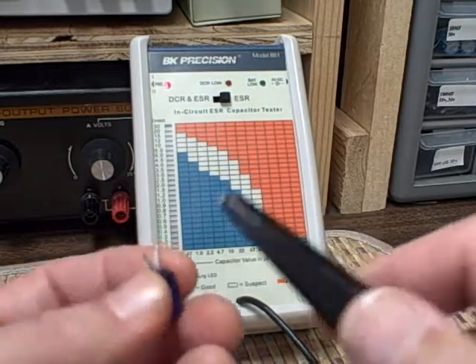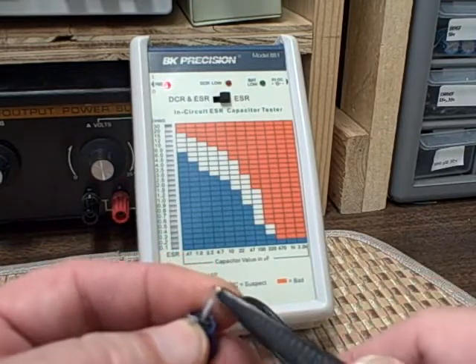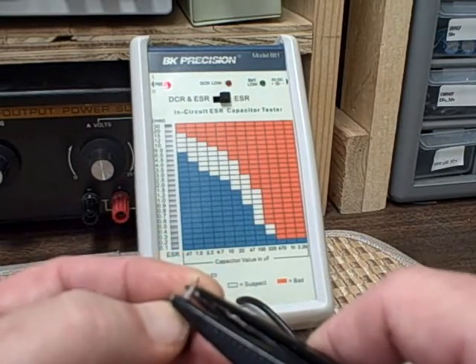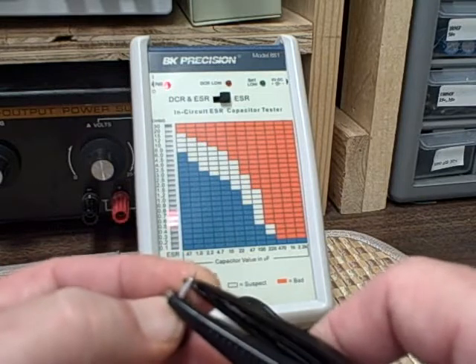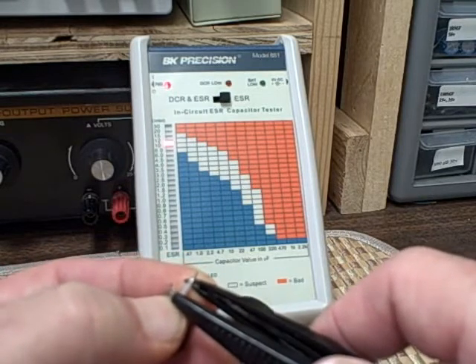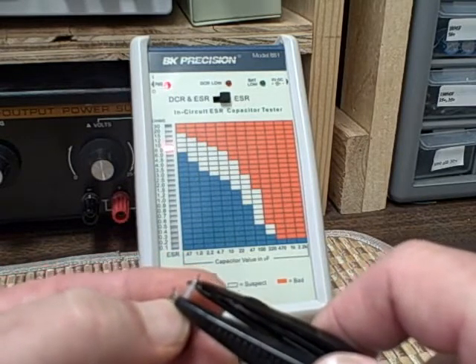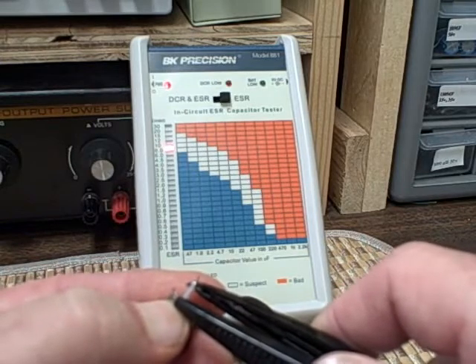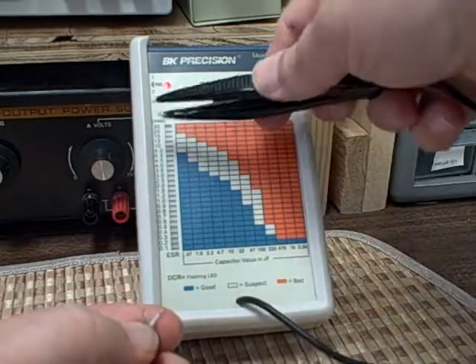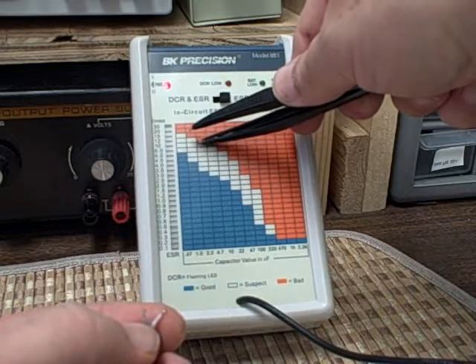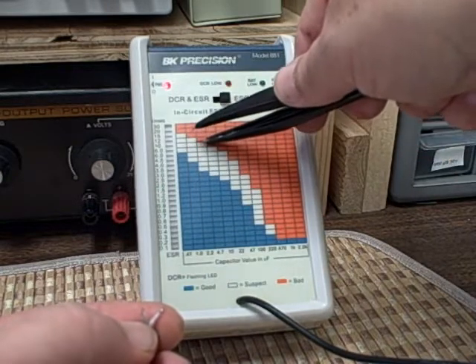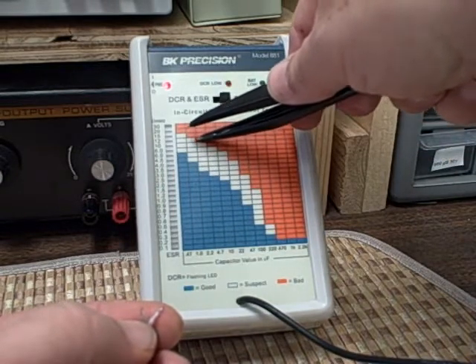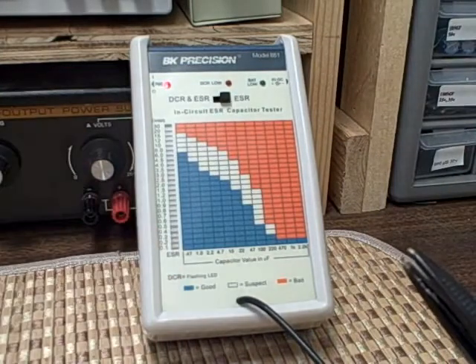Here's another 2.2, 450, reading about 10 ohms. 10 ohms up here, 2.2 is in that column, we are right against the bad, so I'm going to consider that definitely a bad one.